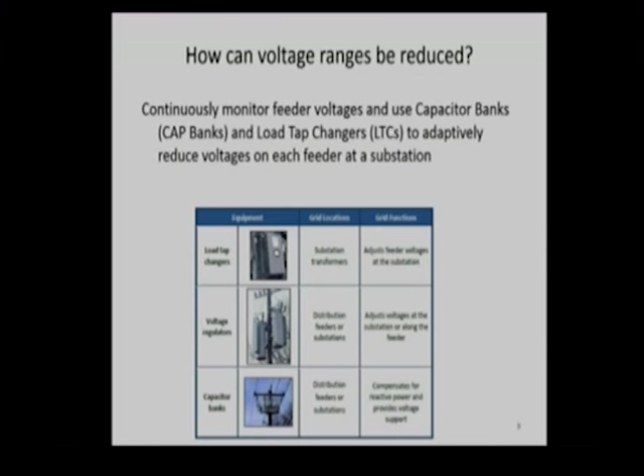The other primary element in this is capacitor banks. And if you know what you're looking for, sometimes if you're driving down the road, you can see some big equipment up on the telephone or power poles. And sometimes those are capacitor banks. They're used to help the power quality of the grid and to also provide voltage support. So they tend to boost up the voltage when it's low in a particular spot. Voltage regulators are used less commonly out in the grid, but sometimes you will actually need to reduce the voltage in a particular spot, and a voltage regulator is generally used for that purpose.